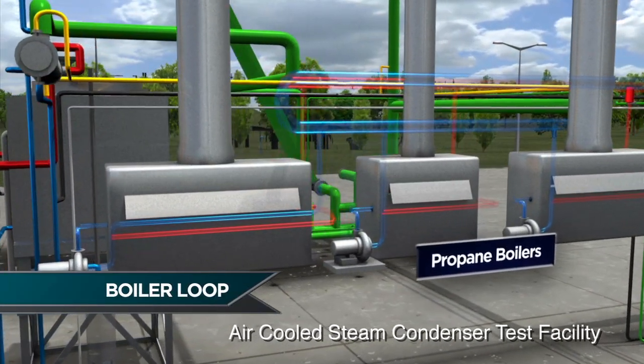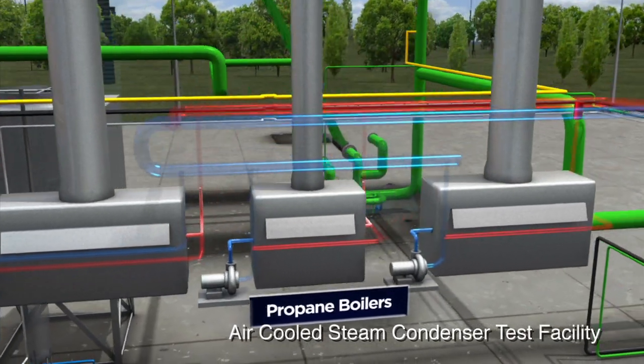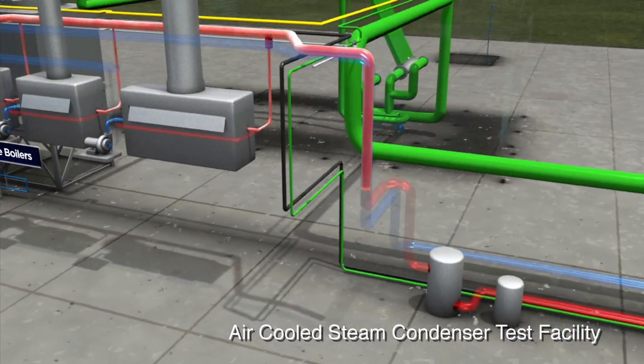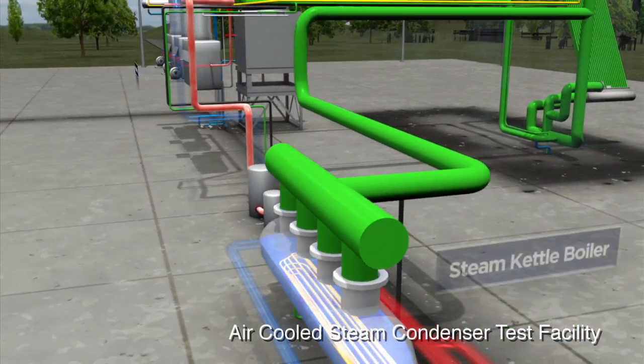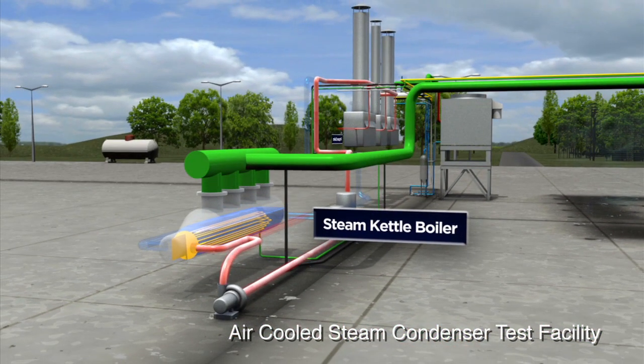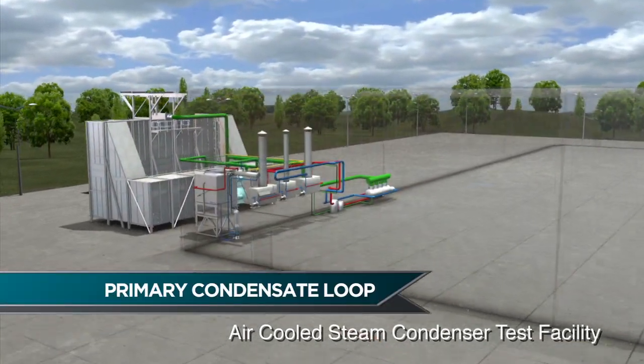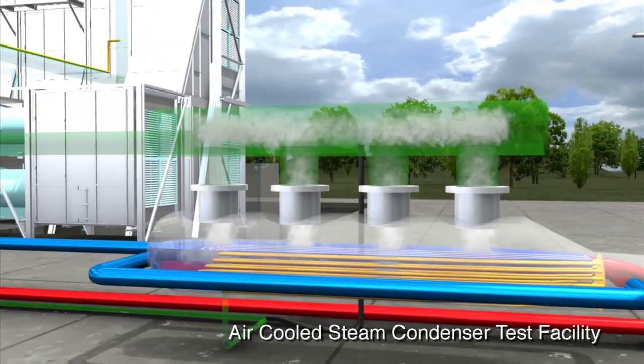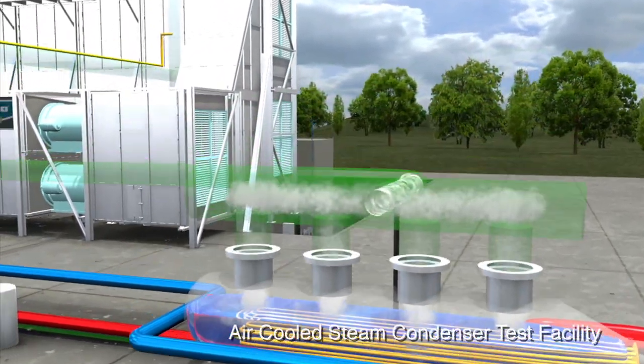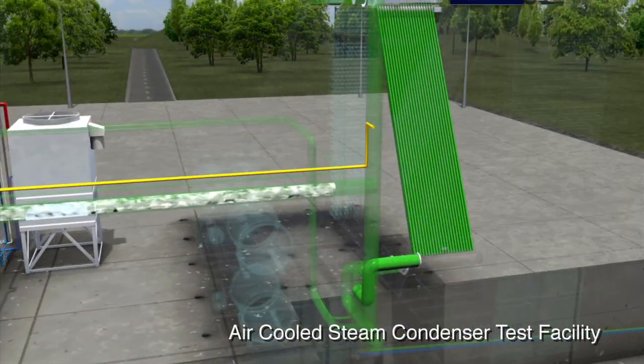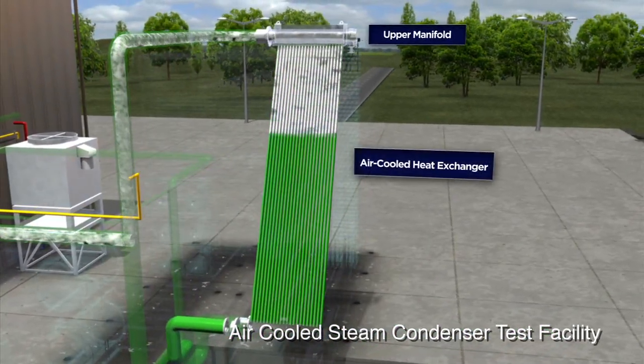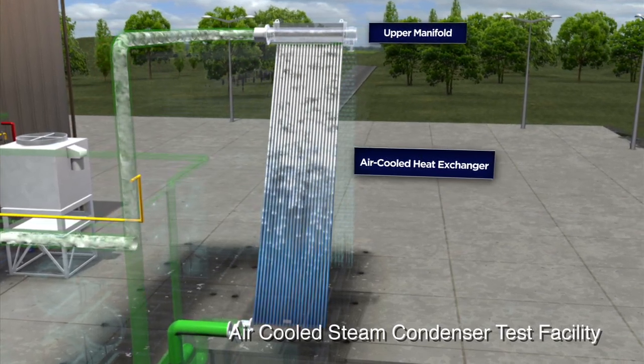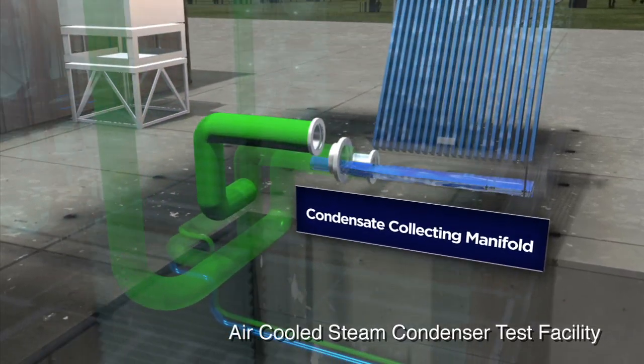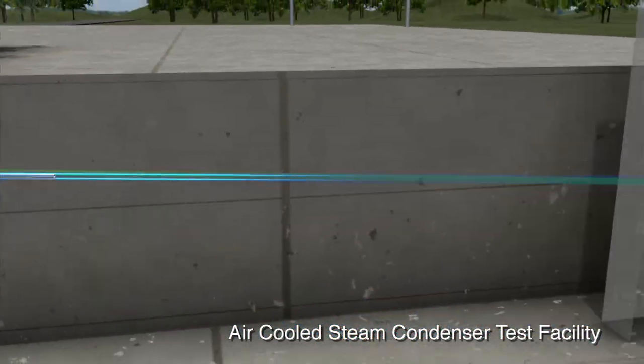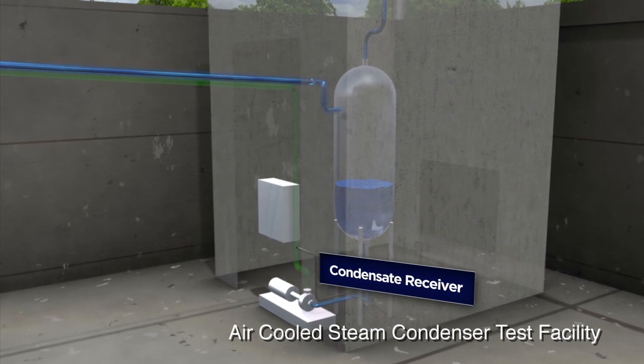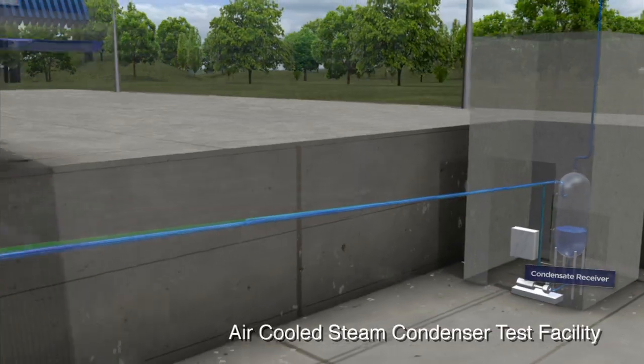The process of testing full-scale air-cooled condenser bundles begins with the boiler loop. The heat load is provided by 3 propane-fired boilers which create hot water that is fed to the steam kettle boiler. The hot water transfers a portion of its heat, generating steam, which exits the kettle through the upper manifold and flows out through the large diameter steam duct to the top of the air-cooled heat exchanger. The steam is condensed in the air-cooled heat exchanger, where it is collected in a condensate collecting manifold and drains into the condensate receiver. The condensate is then pumped back and recirculated to the steam kettle boiler, completing the loop.